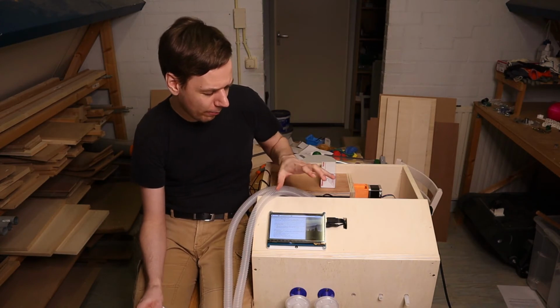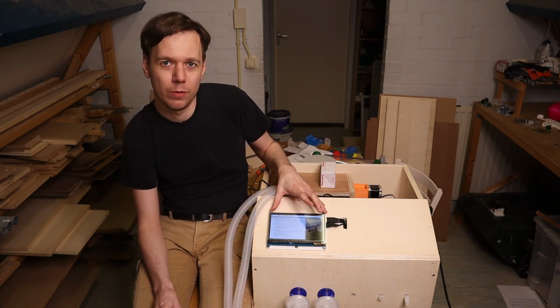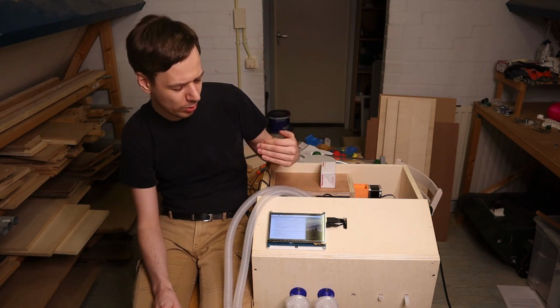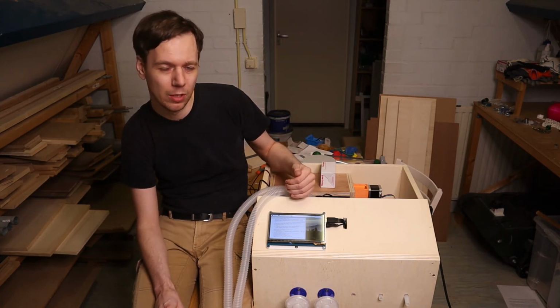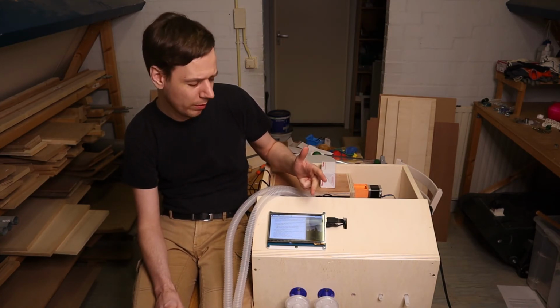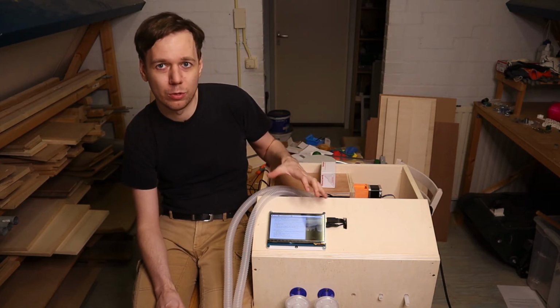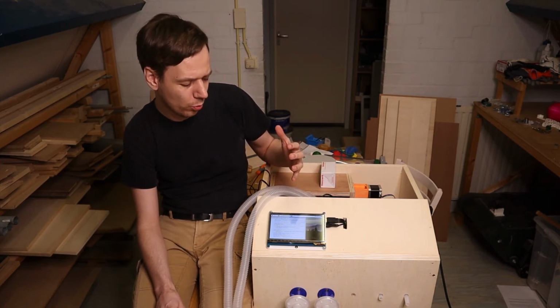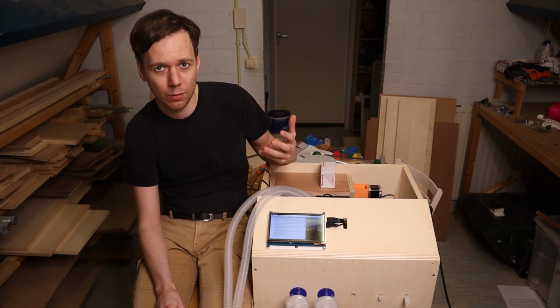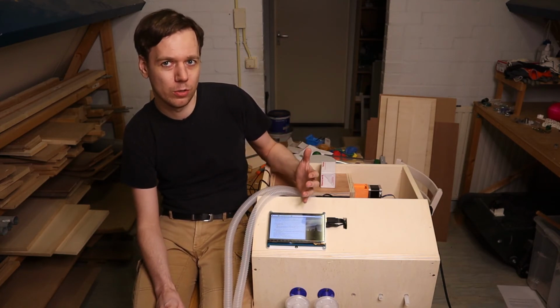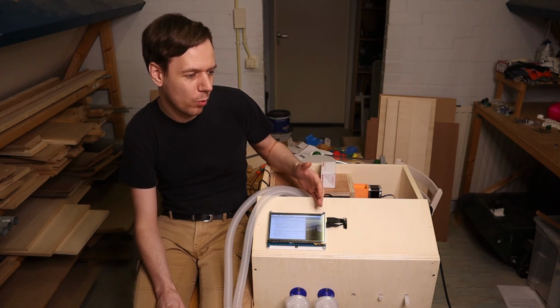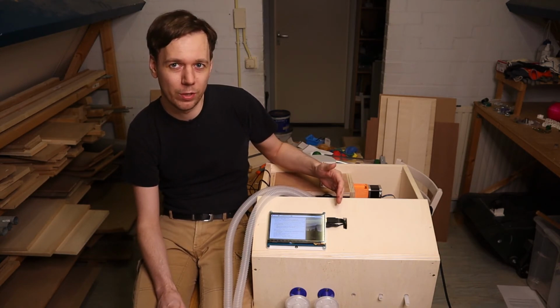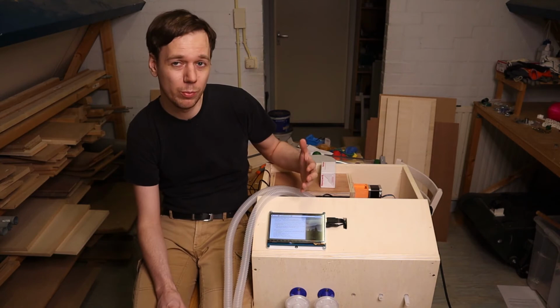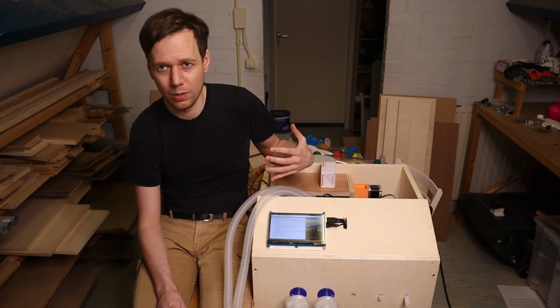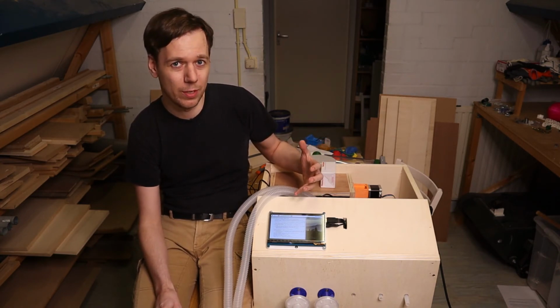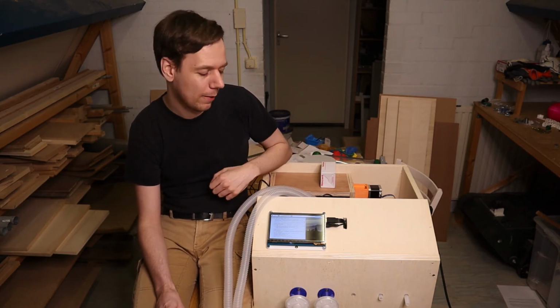And finally, what I mentioned before is the reason you want one of these color screens is because you want to provide live updating graphs of the pressure, flow and volume, because that allows a physician or a nurse to get an idea of how a patient's lungs are doing. For example, if you're applying a relatively high pressure but you're not getting that much volume in a pressure targeted mode, you would then conclude that the patient has very stiff, very non-compliant lungs.